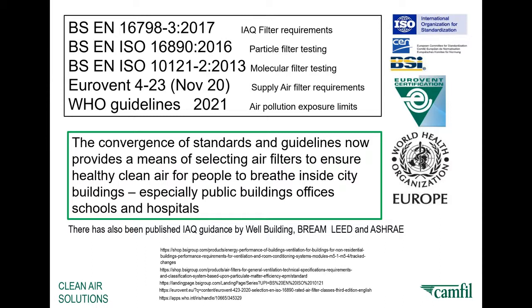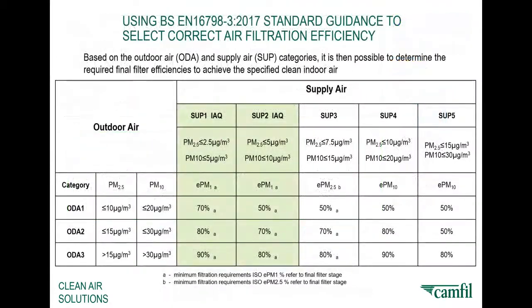And let's get it absolutely clear. It is clean air that is healthy air. And so air monitoring indeed has become another requirement now, given the better technology that's available. This just gives you a quick idea of the difference. SUP is supply air coming through the ventilation system into the building, hopefully having been filtered. ODA is the outdoor air. So the difference between the two, if you like, is the difference a good air filter can make in terms of cleaning the air.